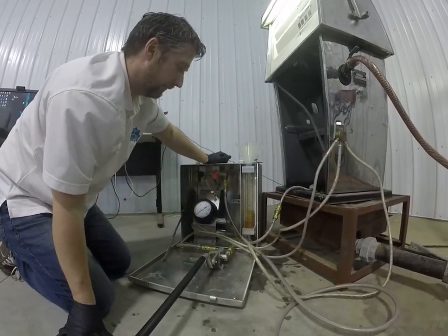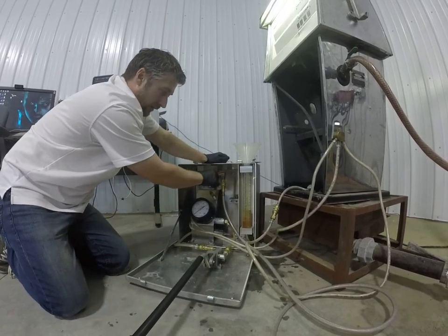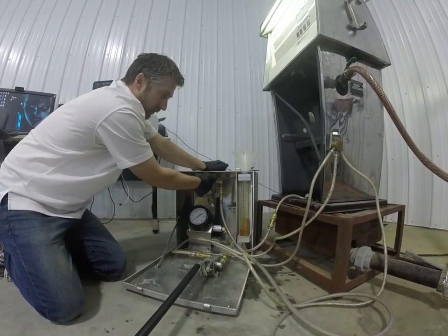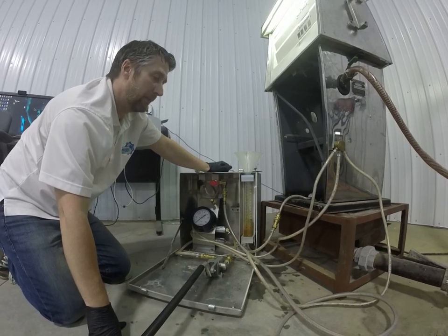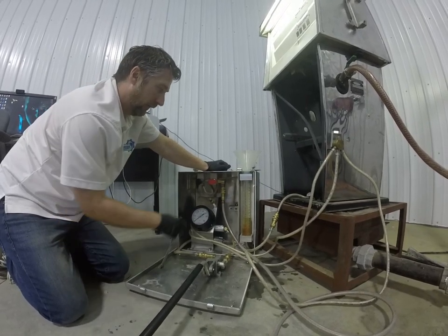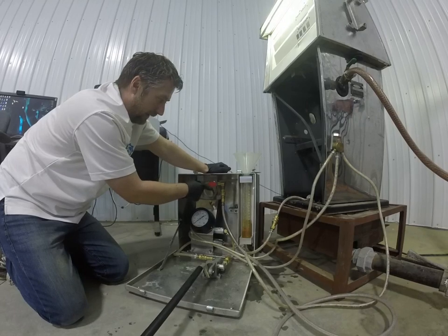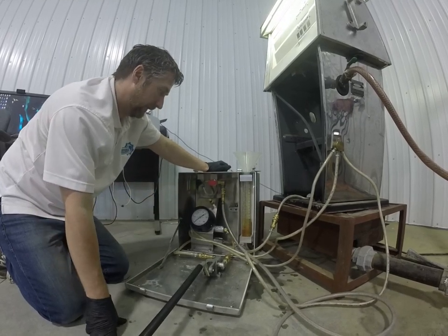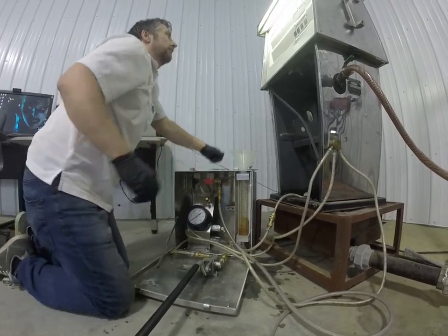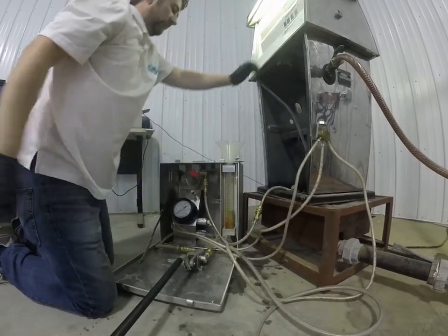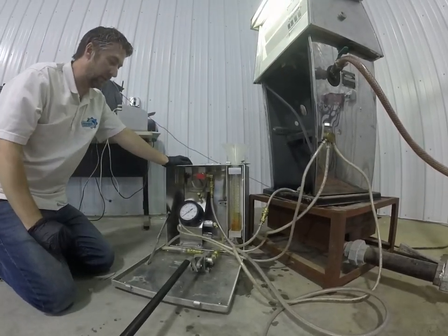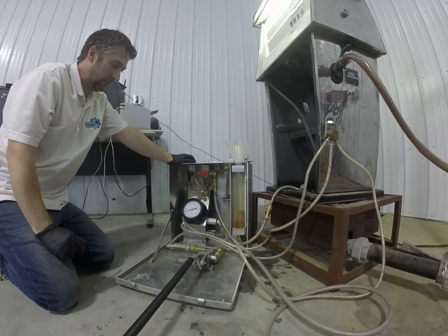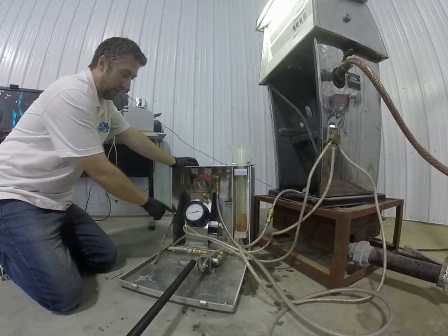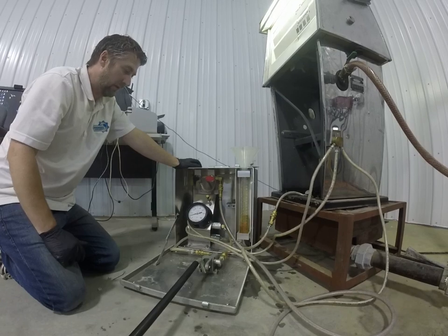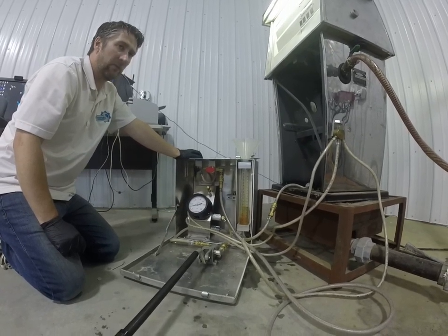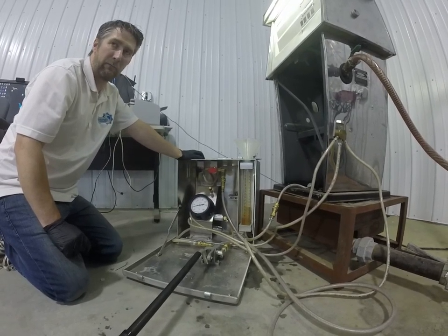Now we're going to turn the red valve towards the drain hose. This will allow the leak, when we start the dispenser, to flow out through the calibrated leak into an approved safety can. Start the dispenser, and then we should see the leak detector kick in, and we'll see that it maintains the slow flow position. This slow flow position should stay there as long as our leak is present.